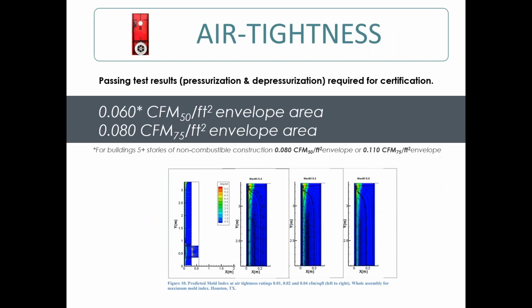Air tightness is the next main performance metric. It is required to have blower door testing, both pressurization and depressurization, and you must pass, so it's pass-fail. The main certification target is 0.06 CFM50 per square foot of envelope area. It's not volumetric, it's not in air changes per hour, it's per square foot of envelope. And again, this is based on building durability rather than volumetric, which could lead to very different air leakage per square foot of building envelope when you get to different size buildings.